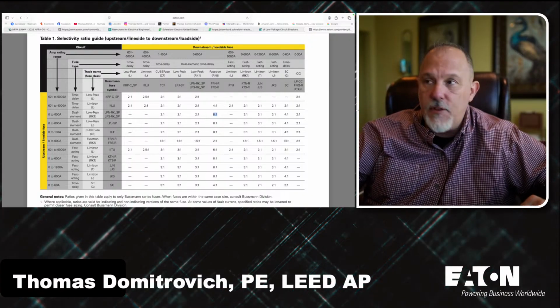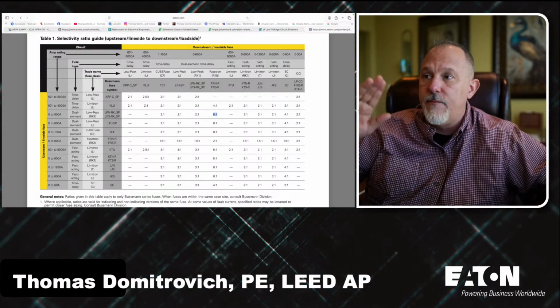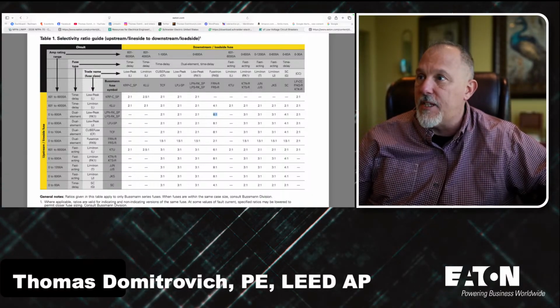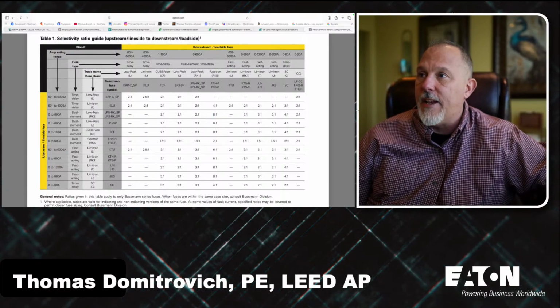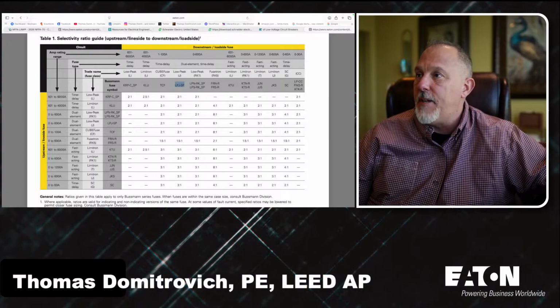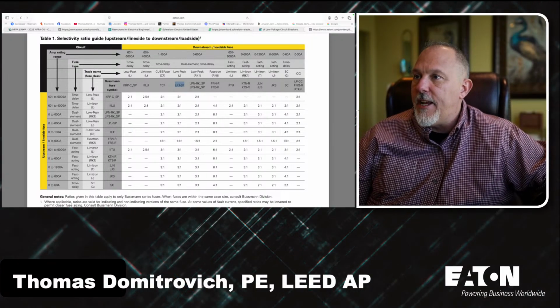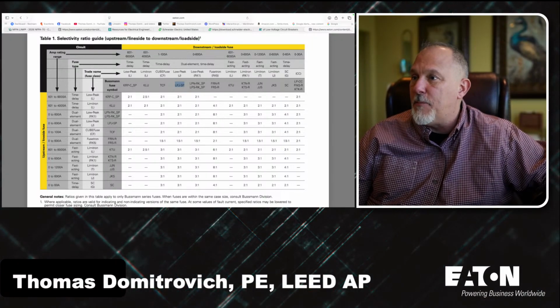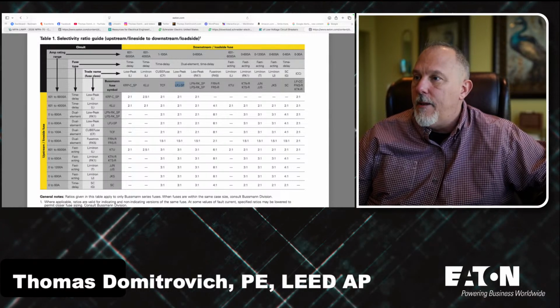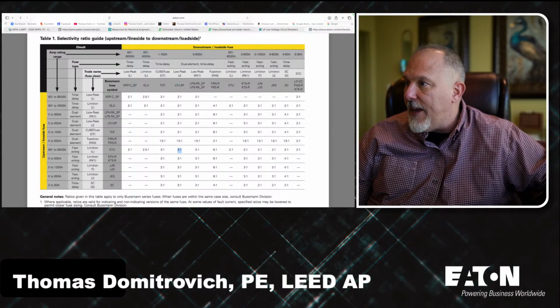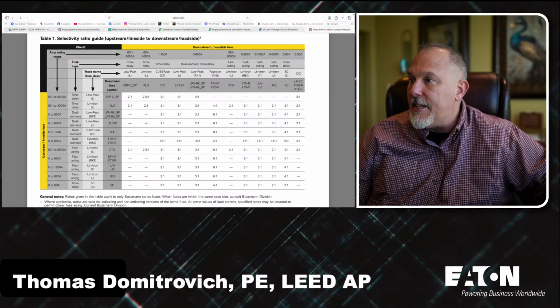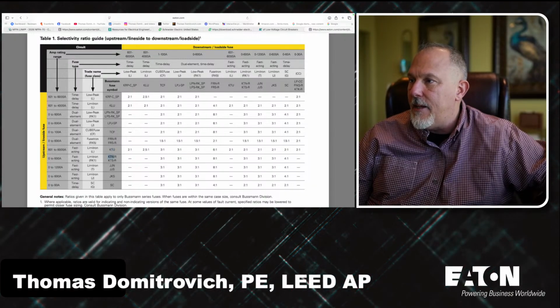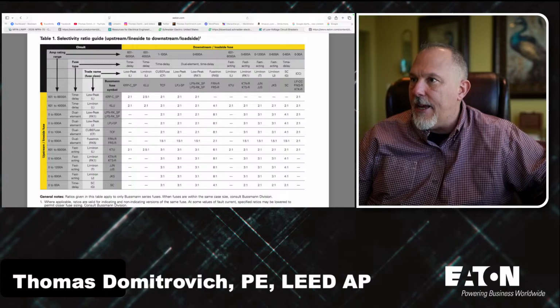The fast-acting fuses are that way. You'll see a lot of 2 to 1s. If I've got an LPJ downstream, I can put an LPJ upstream at 2 to 1. It even gets better at 1.5 to 1. Now here's a 3 to 1 if I have the KTUs or a KTN, a JJN, JKS.